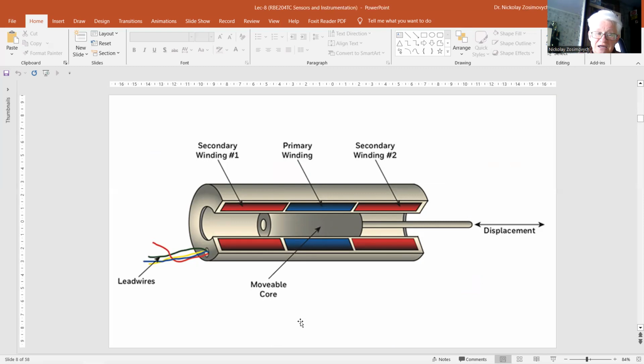The LVDT is operated with an AC voltage. Its amplitude and frequency can be chosen by the user within a wide range. Typically, it is from 1 to 10 volts and 50 Hz, maybe up to 10 kilohertz. Its sensitivity is expressed in millivolt output per volt of input and per meter of displacement, as units with meter.